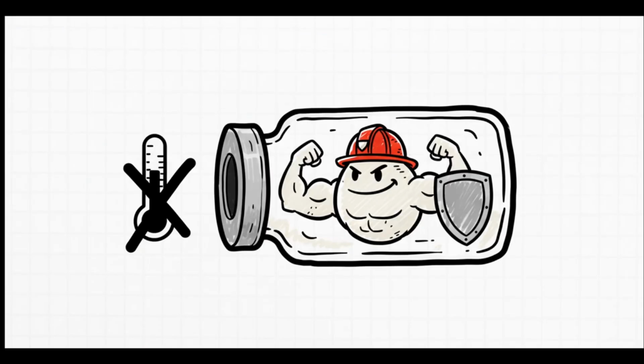The PQ test doesn't just rely on temperature probes anymore. It uses the real enemy: live microorganisms. Specifically, these little vials that are packed with a known quantity of Geobacillus stearothermophilus spores. These things are legendary for being incredibly tough to kill with heat. The thinking is, if you can kill these, you can kill literally anything.